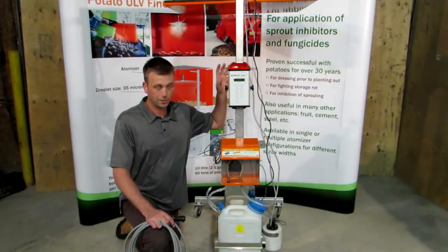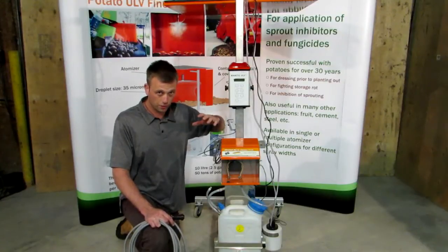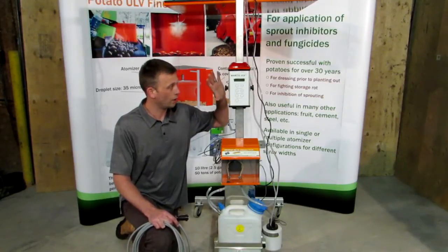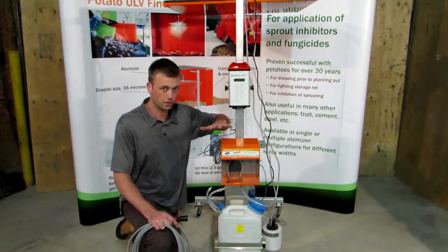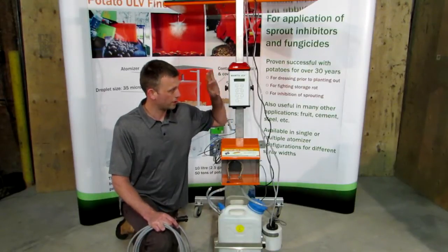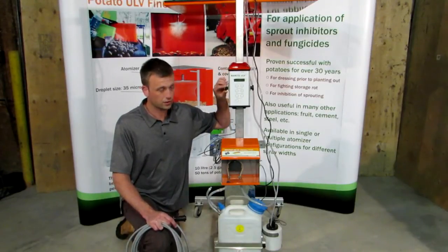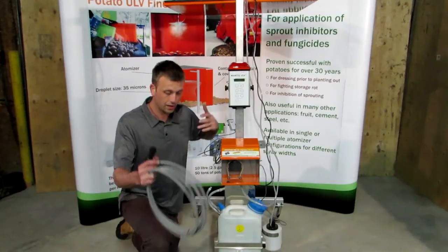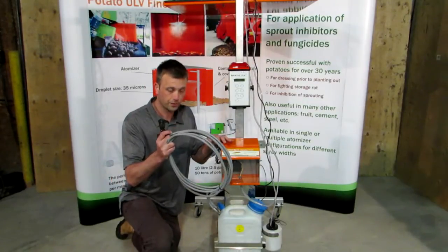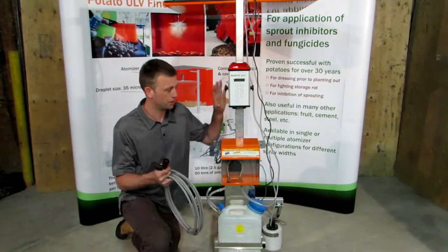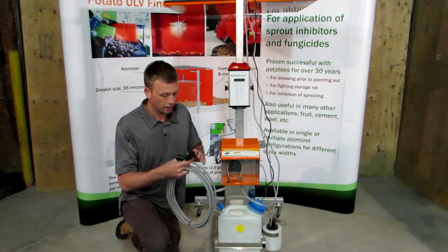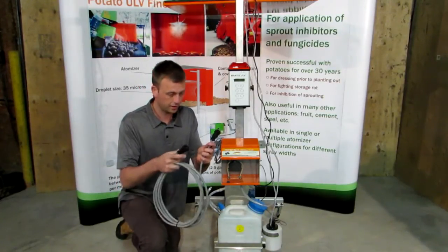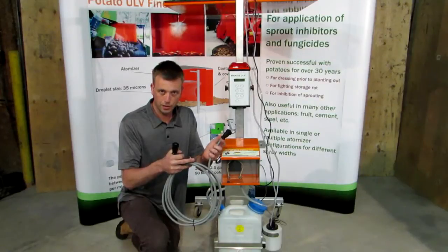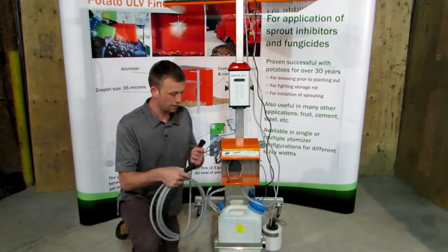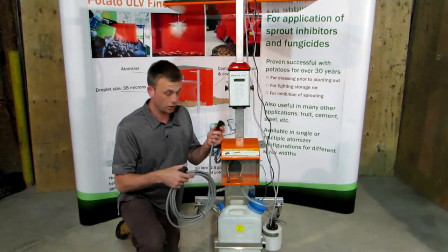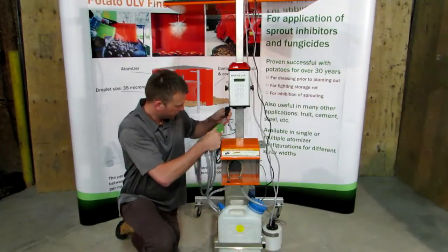Now that we have the atomizer and, if needed, the flow sensor wired in, we'll wire the control box to the pump box. The control box comes with a mounting bracket and bolts, so you can put that anywhere. It comes with a 5-meter cable, so you can put it wherever it's convenient for you. This cable is double-ended. It doesn't matter which way it's connected, and of course it only fits in one way. So I'll hook that up.